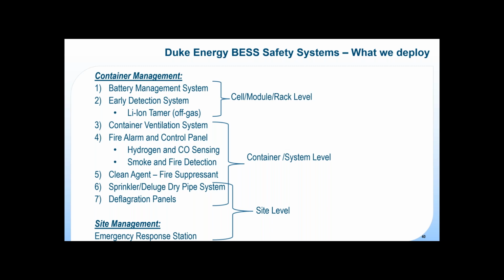Hopefully at that point we've got the system under control, but should we not, and need to deploy water, we've got a sprinkler or a deluge dry pipe system piped into all of our containers on these sites. A line runs out to the emergency response station, and a tanker can be hooked up from the fire department, and we literally can flood these containers if needed.